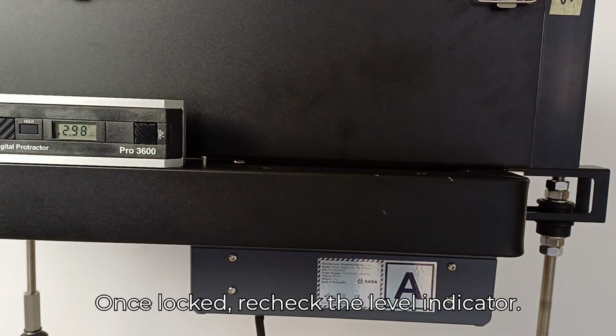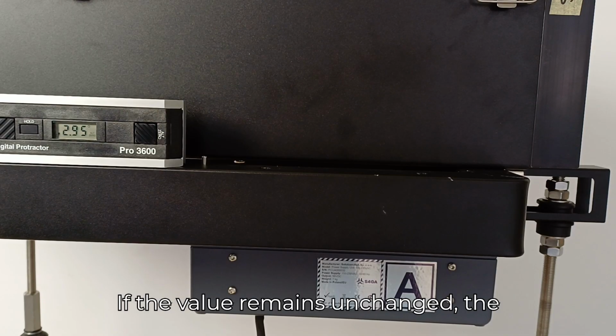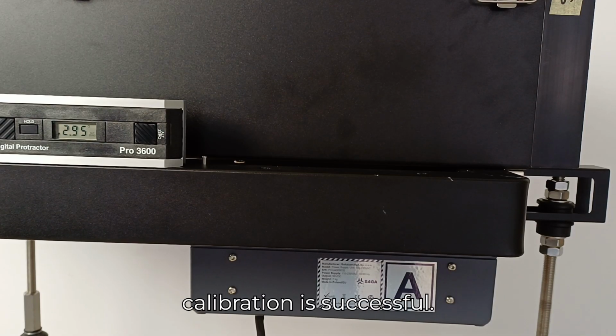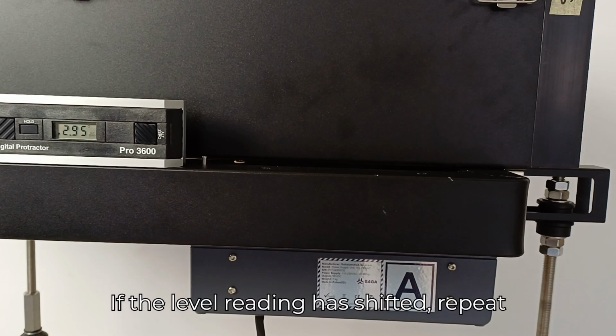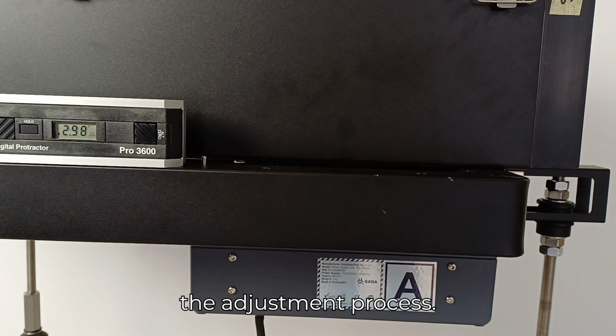Once locked, recheck the level indicator. If the value remains unchanged, the calibration is successful. If the level reading has shifted, repeat the adjustment process.